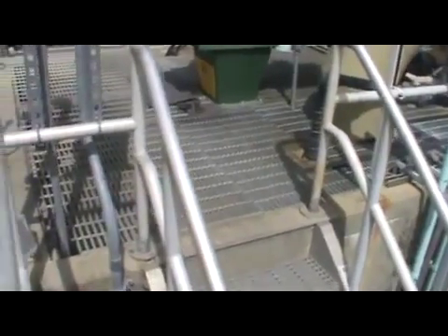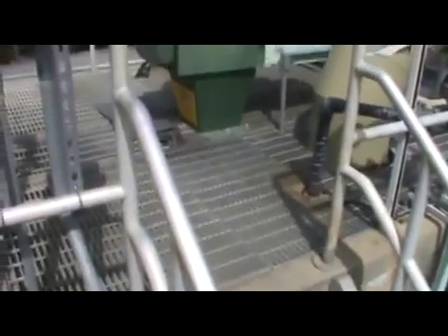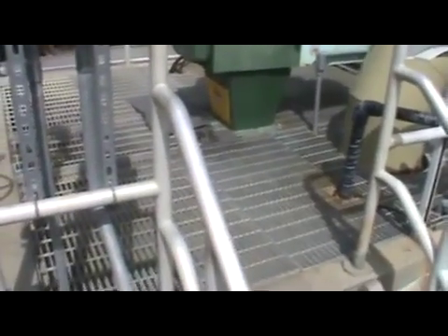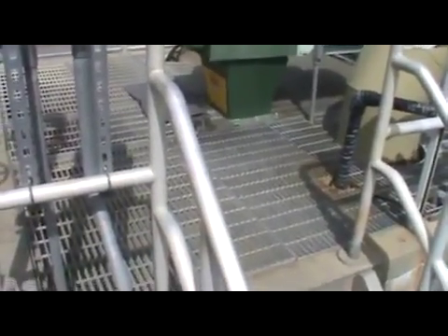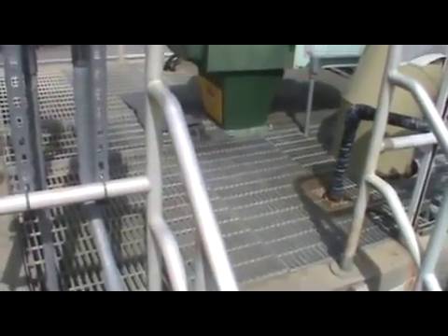So what's going on in this flash mix here is the alum is added to the water, which has a positive charge, and it's being mixed together very, very vigorously. And what's happening is the water and everything in there is banging together, and the positively charged alum in the water is banging around, and it's collecting together with those negatively charged ions in the water and forming flock particles. There's a very exact science to this. Really, the water should remain in this flash mix for the coagulation process no more than about 30 seconds.